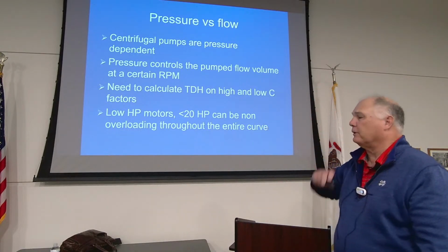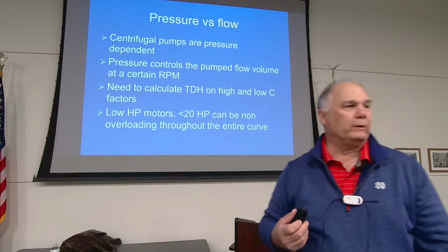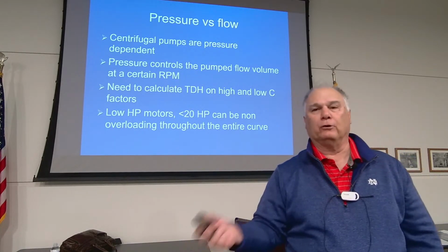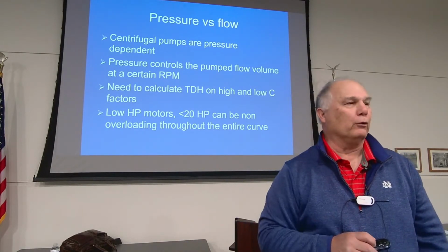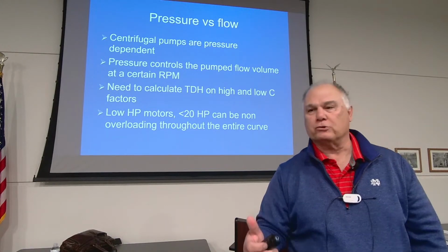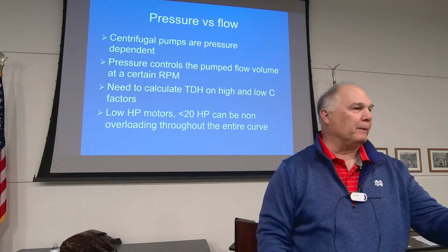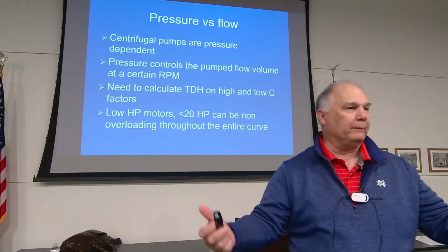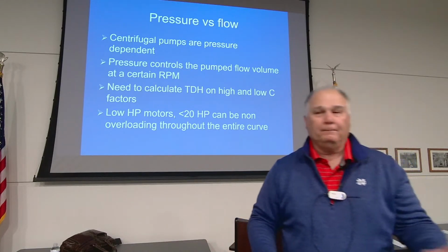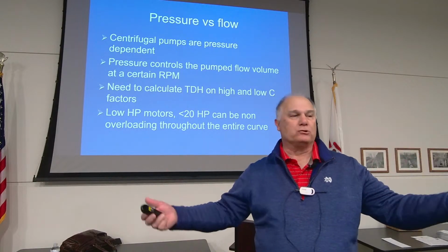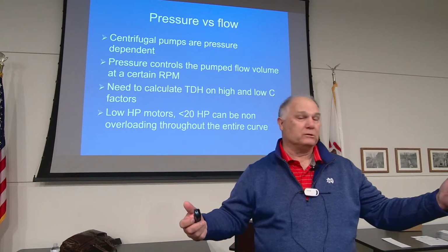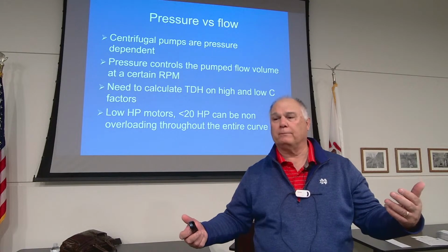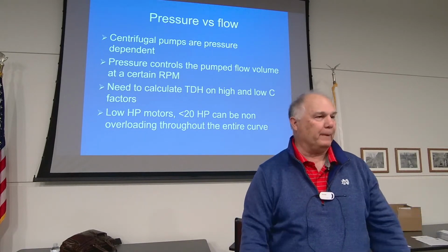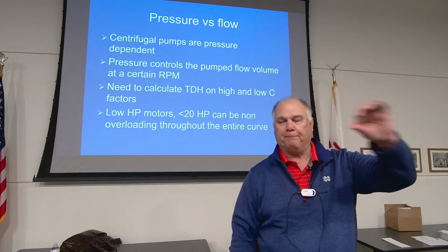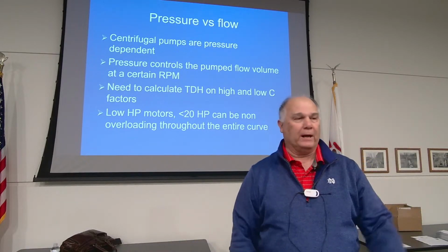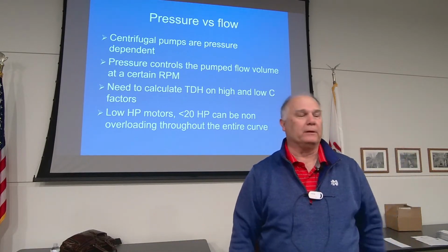And as I mentioned earlier, as a company, for anything less than 20 horsepower, you're going to get a full curve motor. Controls are essentially the same price, whether it's a 10 horsepower pump or a 20 horsepower pump. They're the same price. Unless there's some limitation that the engineer alerts us to, but usually there's not. Wires that big versus that big, it's the same price. We're not talking about wire that's the size of your thumb or anything like that.